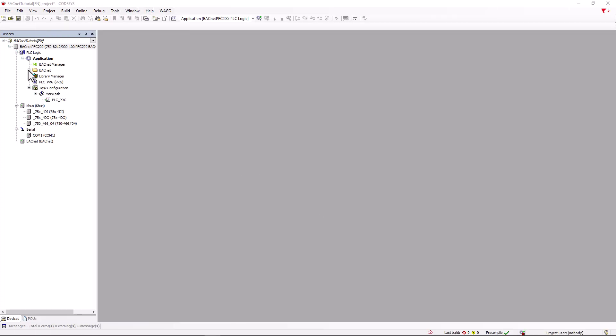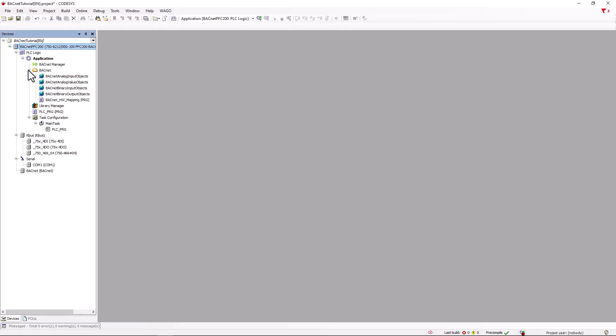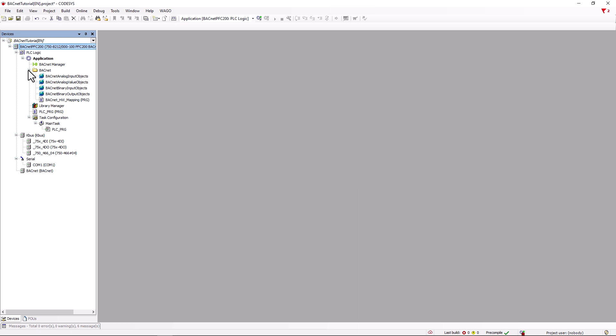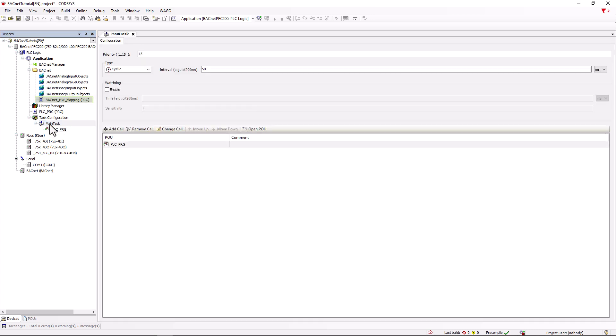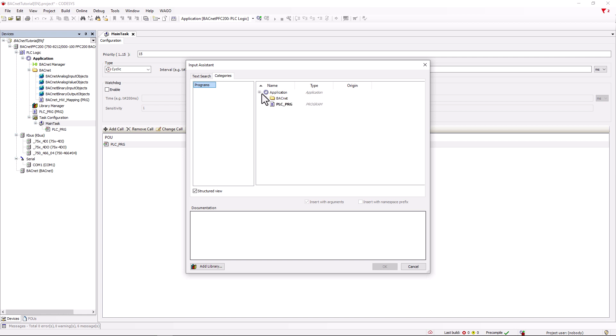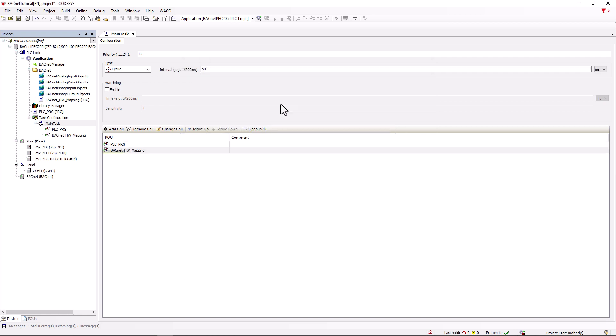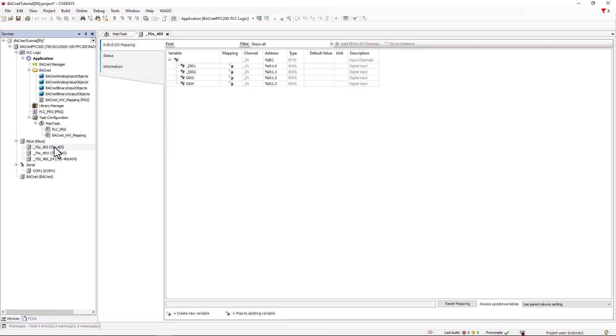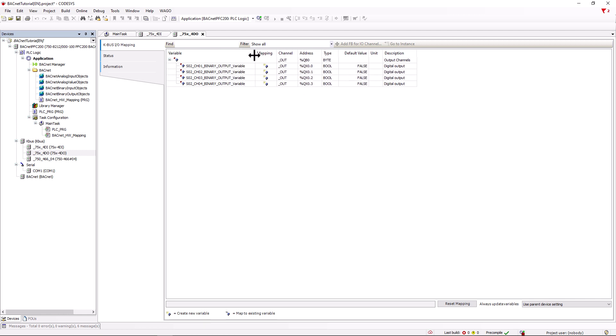Back in CODESYS, we see that a BACnet folder has been created containing the previously selected data points as GVLs. If the inserted GVLs are underlined in red, the library is missing. The program contained in the BACnet folder links the variables of the KBUS view with the created BACnet objects, so it must be called either in the PLCPRG or in the task configuration. In the KBUS view, we can see that variables with a name from the BACnet configurator have now also been entered for the channels that we previously left free.